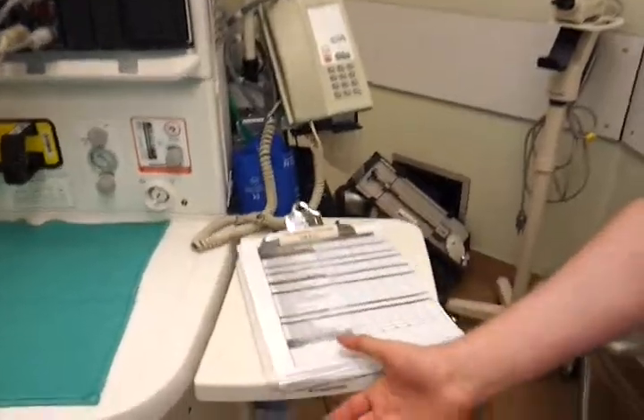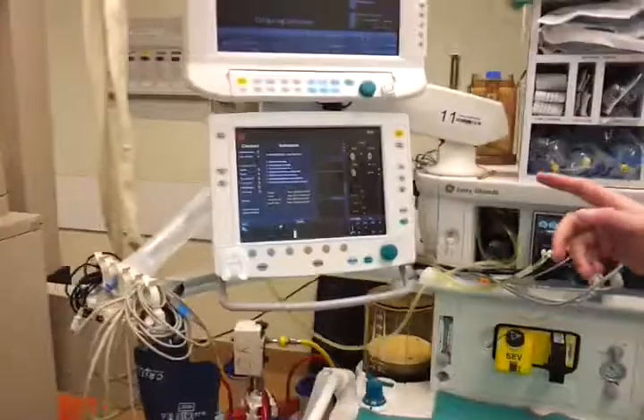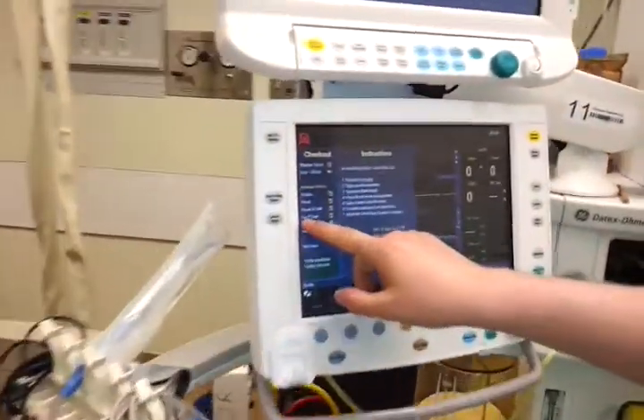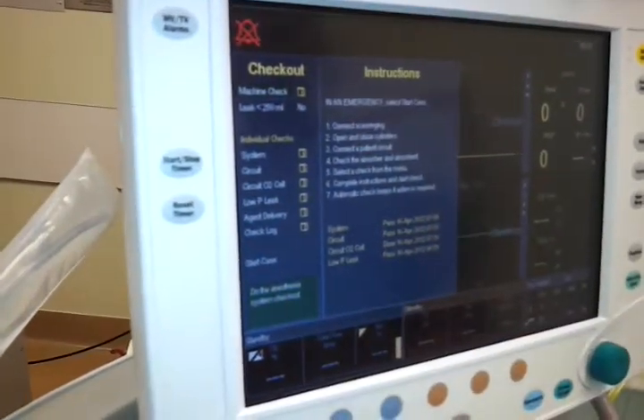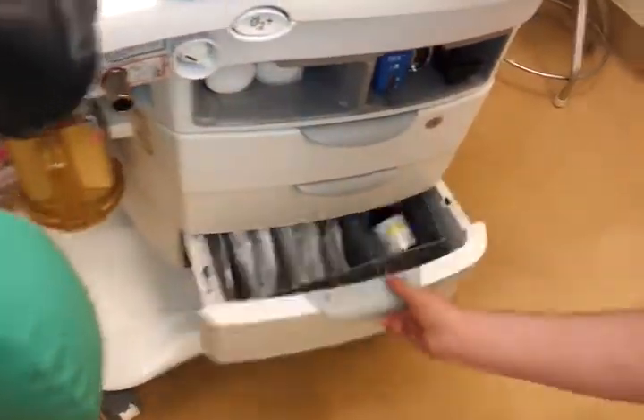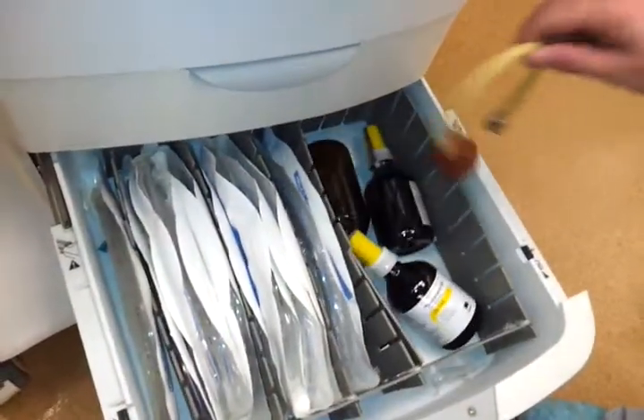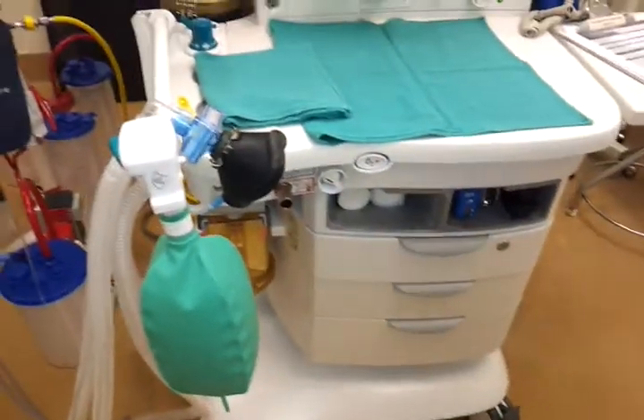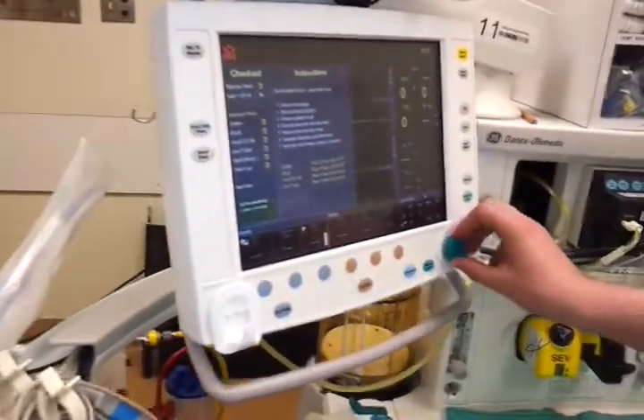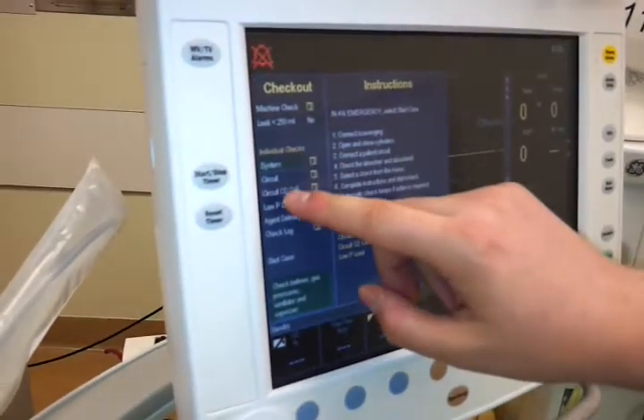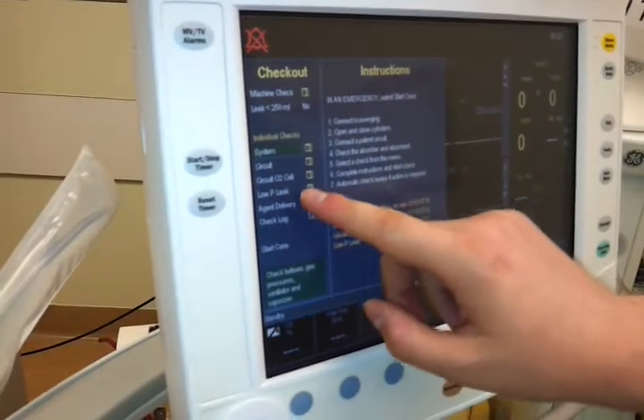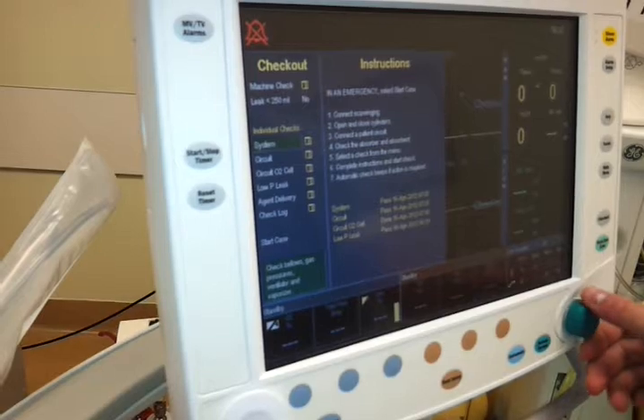Okay, so we're going to show you how to do the actual check first. We're going to bring that over. The very first check that you have to do is the low pressure leak test. So to do that, you need to grab the little bulb, which is always in the bottom drawer down here. So that's this little piece right here. So you're going to scroll down. These are all the different checks you have to do: system, circuit O2 cell, low pressure leak, and agent delivery. And we're going to go through all of them.